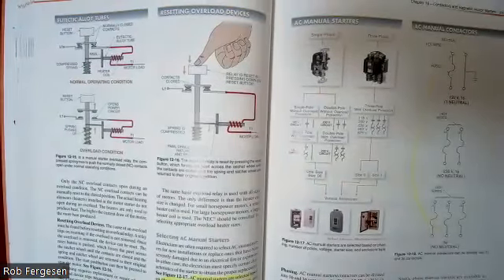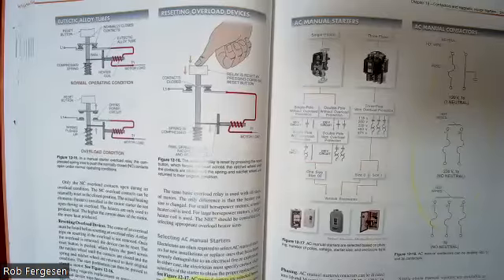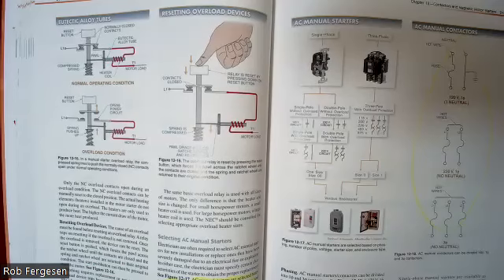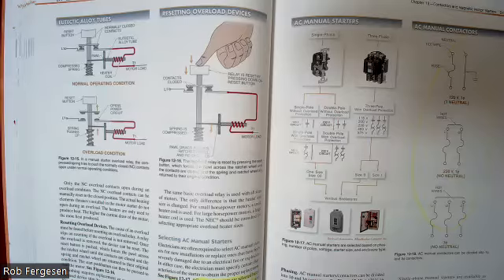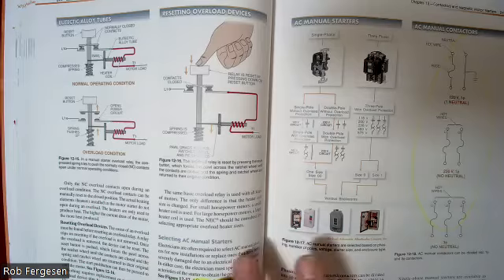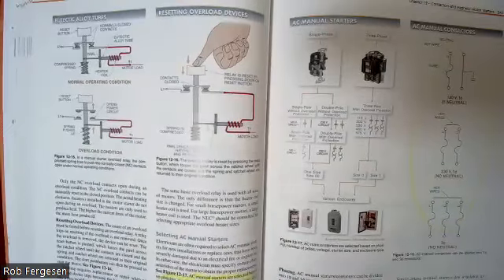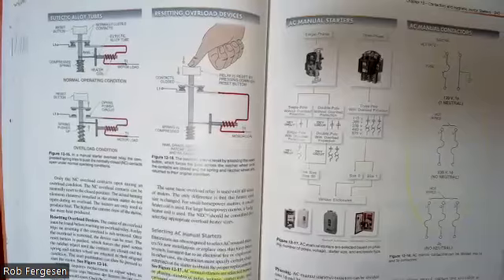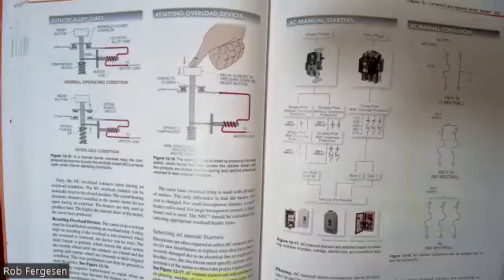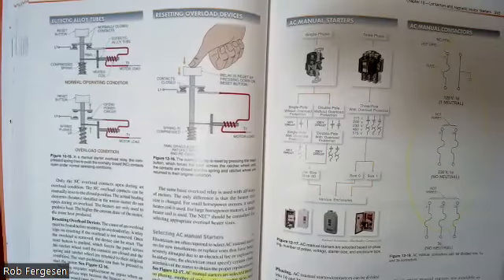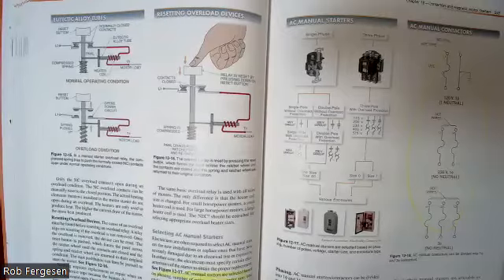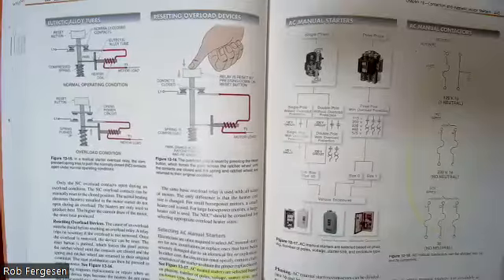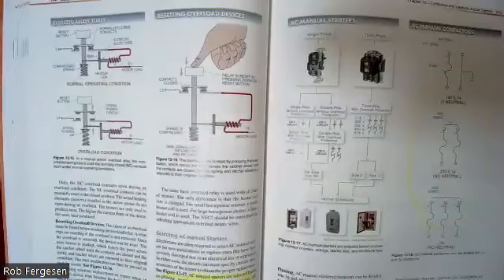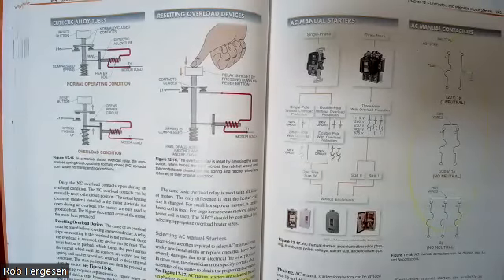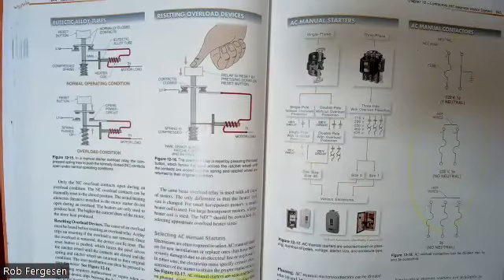On the top of page 244, it talks about a reset button that allows you to reset once that alloy is cooled down. So these are reusable. They're kind of like circuit breakers, but they're old school. They're also very expensive, and you have to buy them separately from the motor starters. In fact, generally speaking, you buy a generic motor starter for a given very broad range of AC motors, either single phase or three phase. Three phase have three big power conductors. And then you buy one of these little overload devices and you install them after the fact. After you buy that, you have to make sure you pick the right overload device to match your motor exactly.